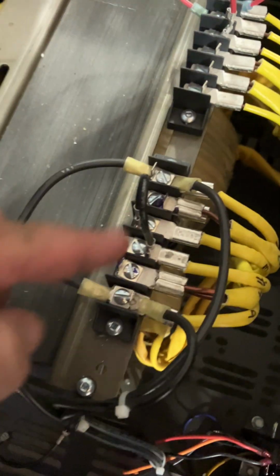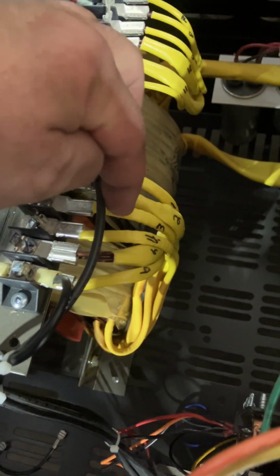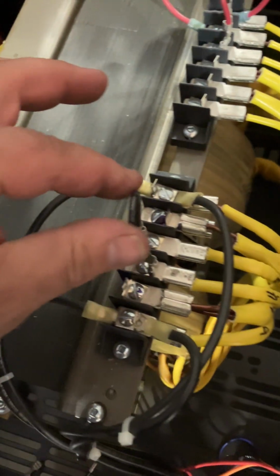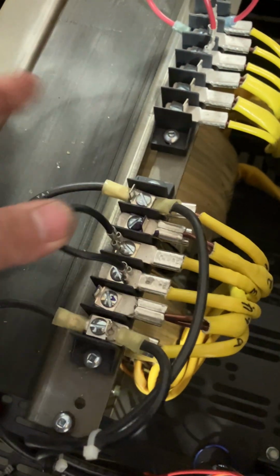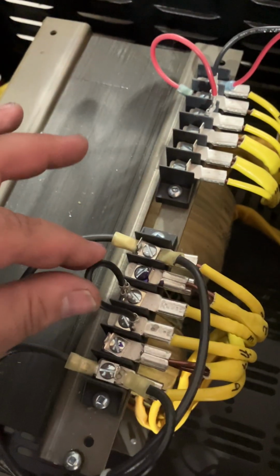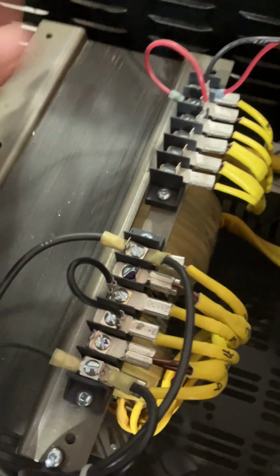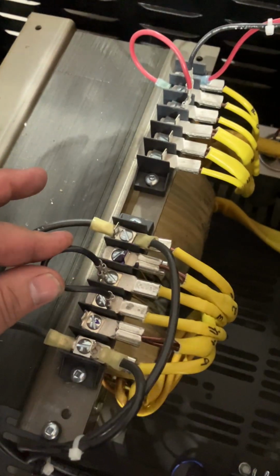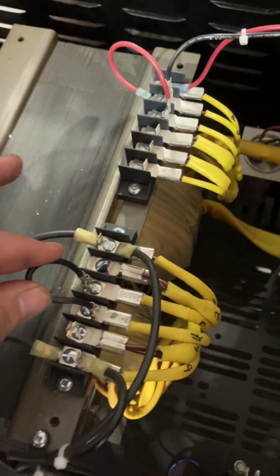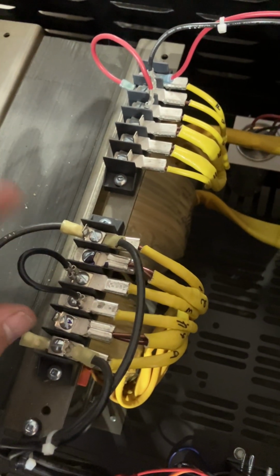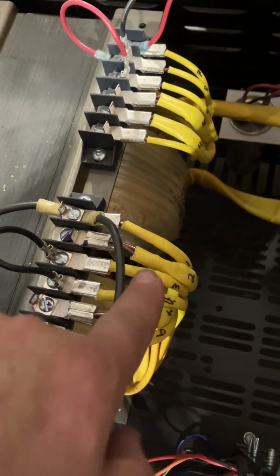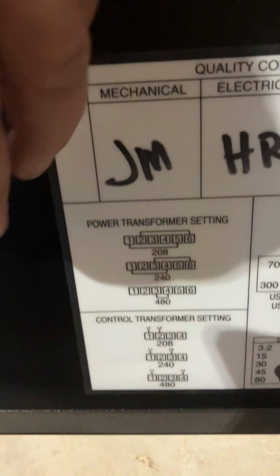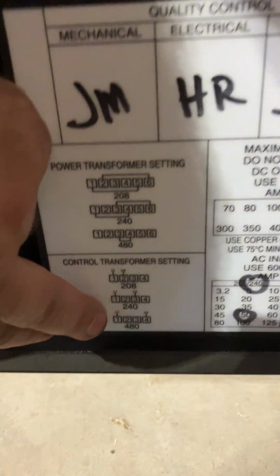Okay, let's go ahead and look at the power transformer. Now, I've already done this, but here's the part we don't mess with, and here's the part we do mess with. And we've got 1, 2, 3, 4, 5, 6. I think I counted right. We put our shorting wire between 3 and 4 because we're feeding everything with 480 volts. I may not understand everything that's going on inside the transformer, but the diagram told me that if we're feeding 480 volts to this thing, which we are, then I need to short between number 3 and number 4, which we did.